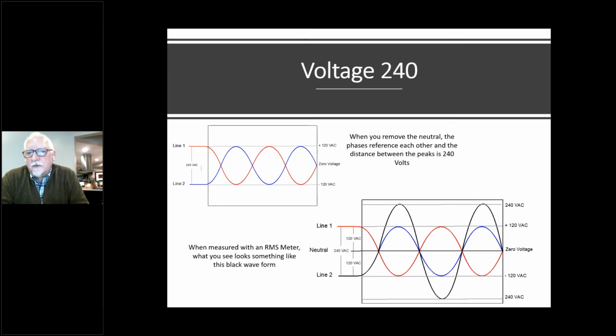Right. So on brewers in the US, for example, there'll be 240 volt heating elements or 208 volt heating elements, but a lot of the components are operating on 110. So in that case, you're supplying a plug, which we'll cover later, that has 4 wires to it: a ground, line 1, line 2, and the neutral. Even though you're getting 240 volts between line 1 and line 2, if you have the presence of a neutral, you can still tap 110 between any one of those legs and neutral. So you basically have a dual voltage machine internally.